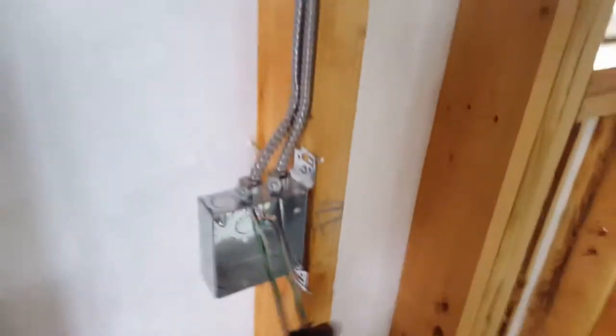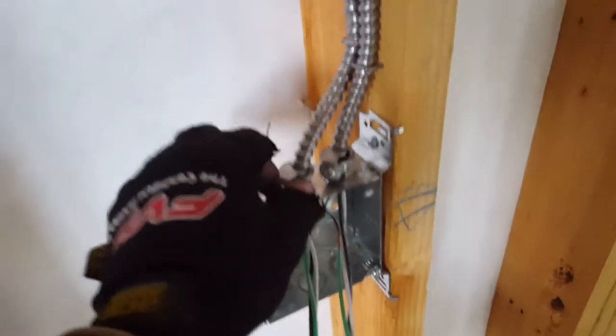This is a plug circuit — it connects all the plugs, going from here, over to there, and all of these will have standard plug receptacles. Every single thing when you're working with MC cable has to have one of these metal boxes, and they take effort to install. To hook up a piece of MC cable to a box, you have to use these special connectors. You punch out one of these knockouts, plug in one of these connectors, screw on the lock nut, then drop the MC cable in the top and tighten it. It's a very slow process, but I enjoy working with MC cable.